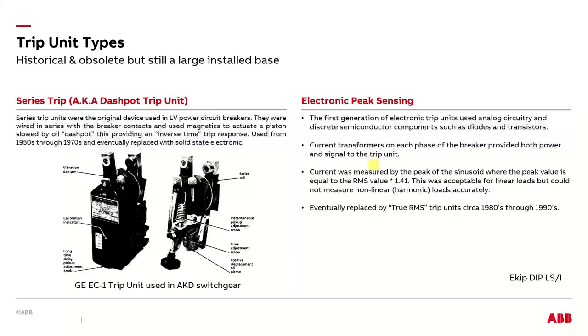They used a series of magnets and dampened oil plungers to provide instantaneous, and then the oil plunger would provide the delay or the inverse time trip response. Really cool things. And if they were maintained correctly and calibrated, they were actually pretty accurate and advanced. But they've all seen their better days. And if you run across any of them, it's probably best to have them replaced. You can usually use the same breaker. So say it's an old General Electric AKD two breaker. You can do a trip unit replacement and put a modern microprocessor trip unit onto an old power circuit breaker.